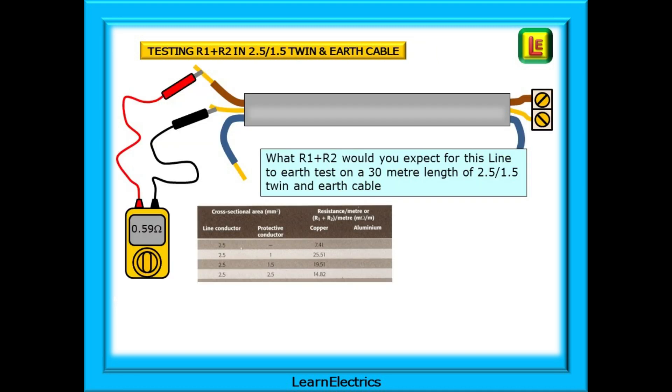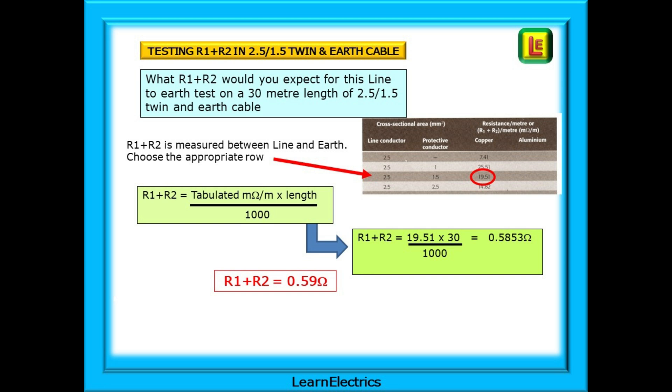We can move on and test two conductors now. Suppose we had a circuit installed in 2.5 square millimeter twin and earth with a length of 30 meters. For standard twin and earth, the line will be 2.5 and the earth or CPC 1.5. Choosing the correct row from the table, we see that the value to apply is 19.51 milli-ohms per meter length of the twin and earth cable.